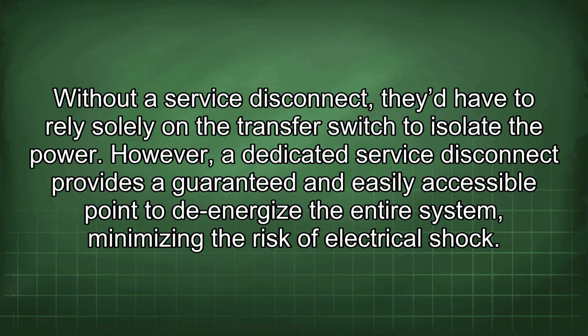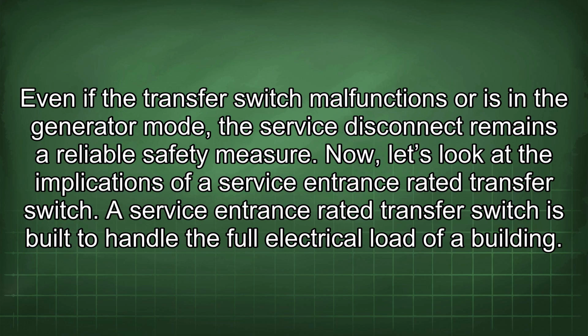However, a dedicated service disconnect provides a guaranteed and easily accessible point to de-energize the entire system, minimizing the risk of electrical shock. Even if the transfer switch malfunctions or is in the generator mode, the service disconnect remains a reliable safety measure. Now, let's look at the implications of a service entrance rated transfer switch.